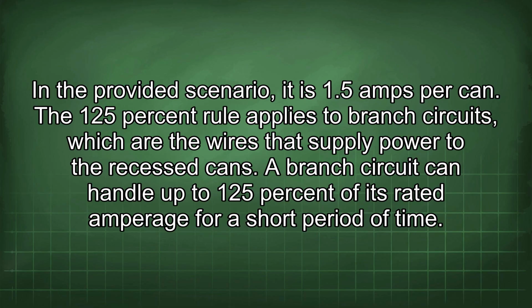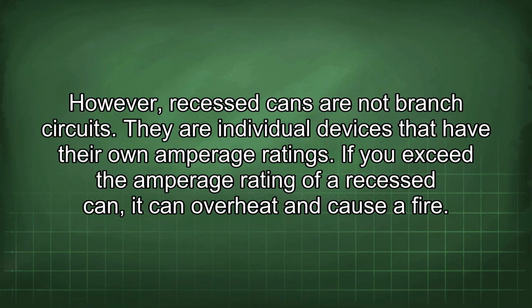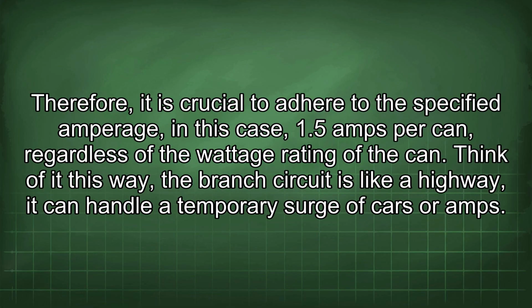The 125% rule applies to branch circuits, which are the wires that supply power to the recessed cans. A branch circuit can handle up to 125% of its rated amperage for a short period of time. However, recessed cans are not branch circuits. They are individual devices that have their own amperage ratings. If you exceed the amperage rating of a recessed can, it can overheat and cause a fire. Therefore, it is crucial to adhere to the specified amperage, in this case, 1.5 amps per can, regardless of the wattage rating of the can.